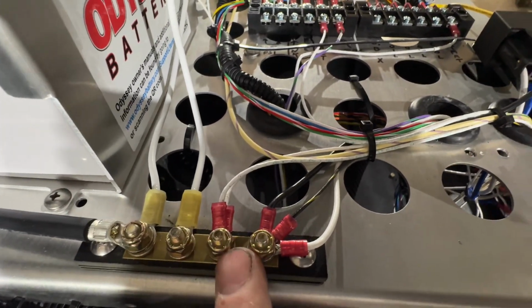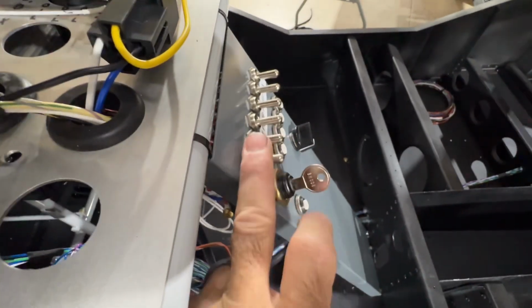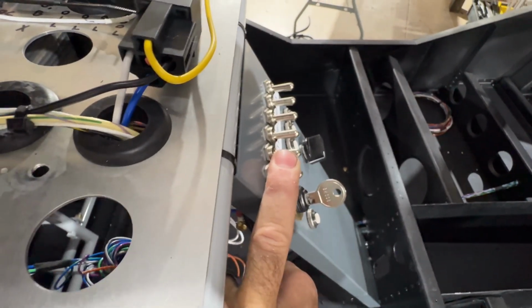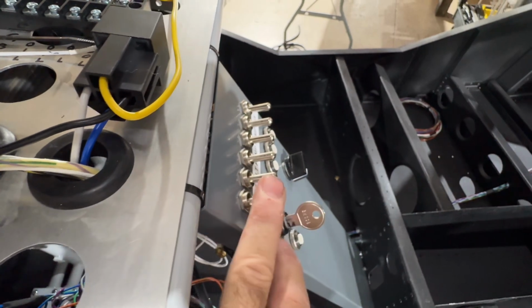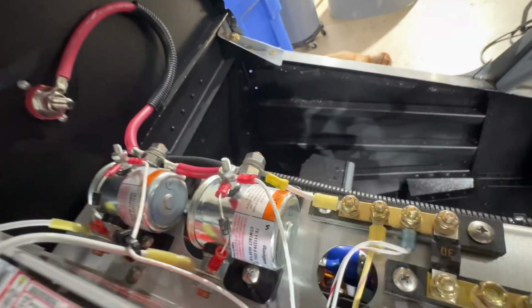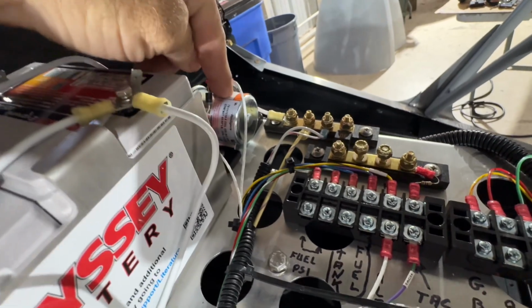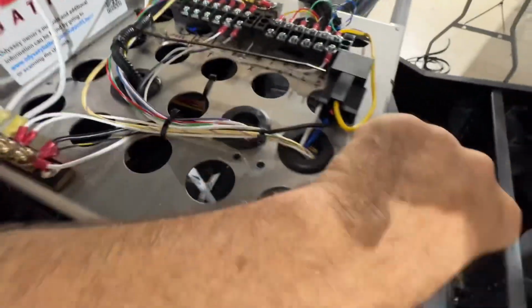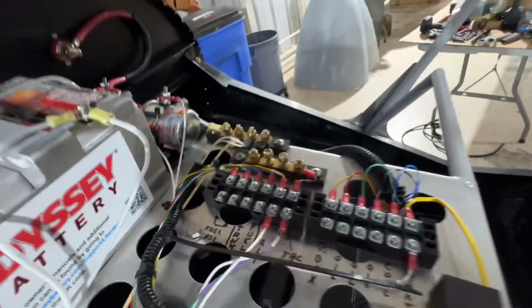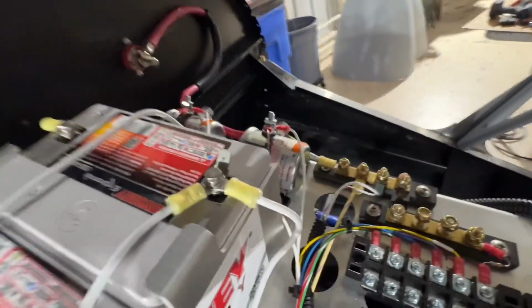Two of them come from these contactor switches, because when you throw one of these switches, you're putting ground to these terminals right here. So it goes from here to the switch to here, and that closes the contactor like this, and the same with the other one — that's how you engage the contactor. So two of these grounds are for that.